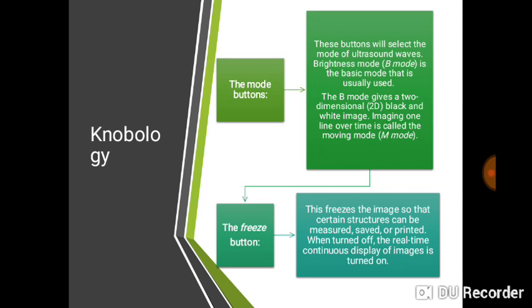You have mode buttons and the freeze button. The mode button allows you to change to Doppler, 4D or 3D (if your machine has it), M mode, B mode, or cardiac mode — whatever mode is available on your equipment. The freeze button makes the image static so you can print or record it.